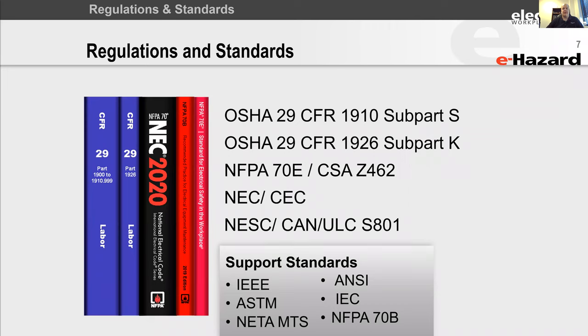That's where we're really looking, when we're working and exposed to the hazards. Either it's an infeasibility issue, where I need the power on to do the task I'm doing, or the equipment is set up such that we can't de-energize it. Something like PD systems or maybe large energy storage systems might be cases where you can't totally de-energize the equipment we're going to work on. So we're going to do that in an energized state.